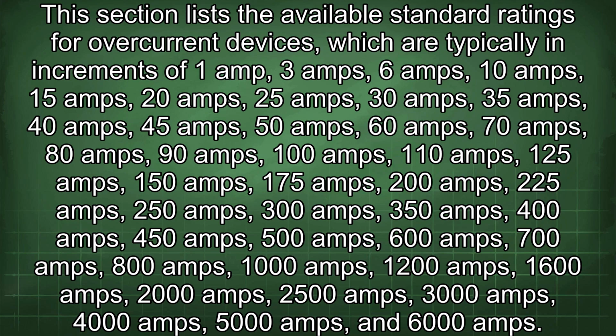This section lists the available standard ratings for overcurrent devices, which are typically in increments of 1 amp, 3 amps, 6 amps, 10 amps, 15 amps, 20 amps, 25 amps, 30 amps, 35 amps, 40 amps, 45 amps, 50 amps, 60 amps, 70 amps, 80 amps, 90 amps, 100 amps, 110 amps, 125 amps, 150 amps, 175 amps, 200 amps, 225 amps, 250 amps, 300 amps, 350 amps, 400 amps, 450 amps, 500 amps, 600 amps, 700 amps, 800 amps, 1000 amps, 1200 amps, 1600 amps, 2000 amps, 2500 amps, 3000 amps, 4000 amps, 5000 amps, and 6000 amps.